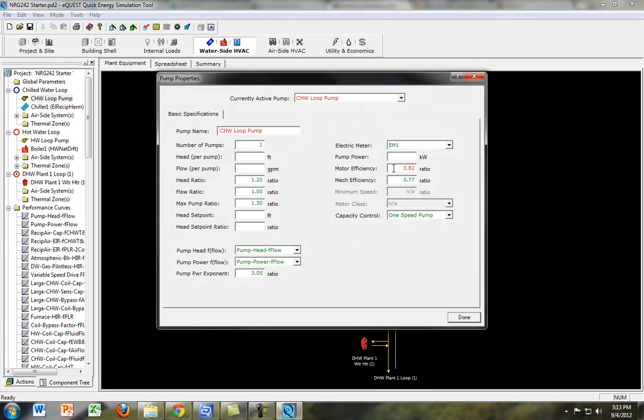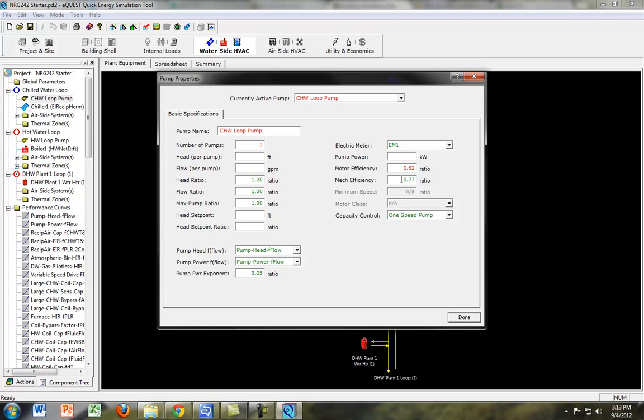And we can see right now we have the motor efficiency and the mechanical efficiency. And the mechanical efficiency, you can see if you stay on there, is the mechanical efficiency of the pump impeller. So the efficiency of the system is those two multiplied together.